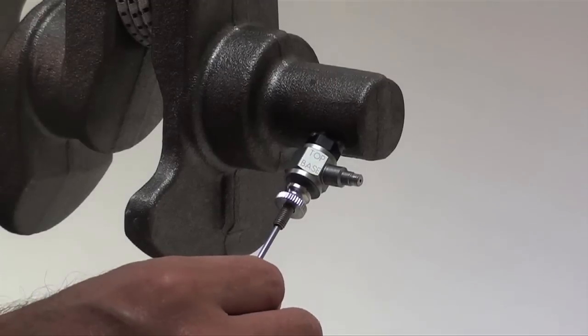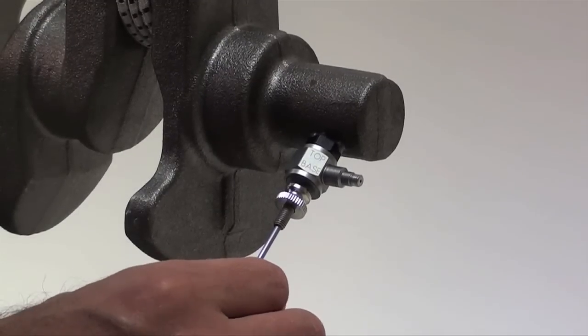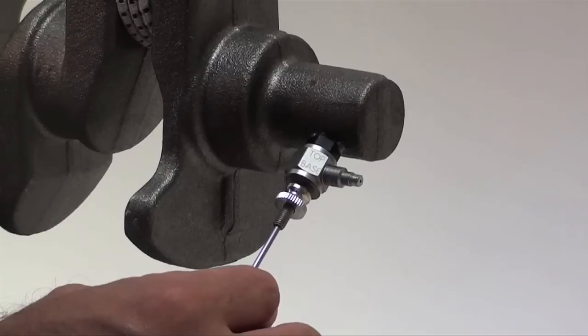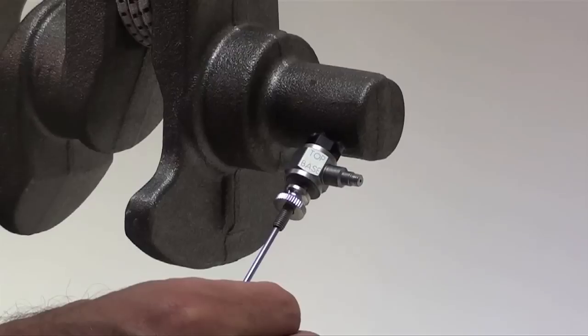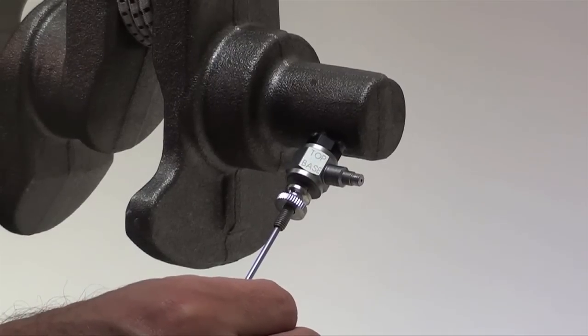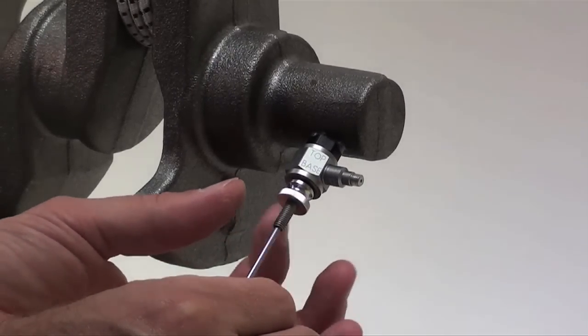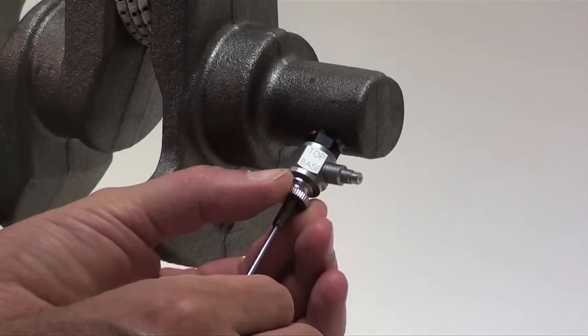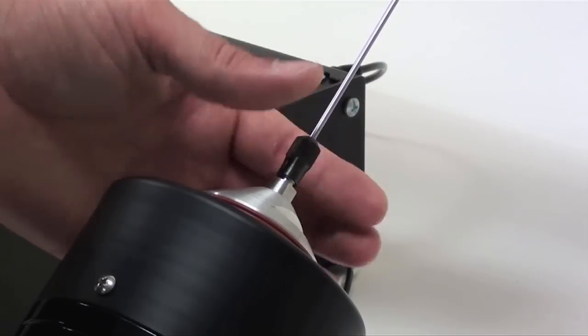So you want to tighten the threaded portion of the stinger into the load cell until it bottoms out, and then back it off by maybe half a turn. And then we'll go ahead and tighten the lock nut. And we need to tighten the stinger in the collet.